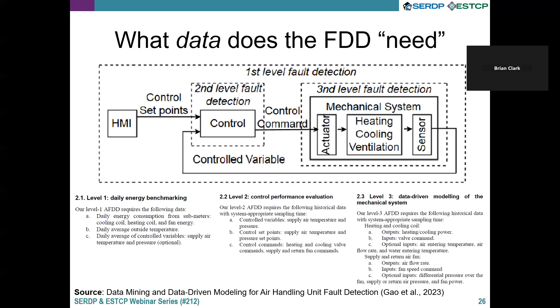So in this study that I'm citing here, shown below, there's even multiple levels of the data collection. There's a first pass in these different feedback loops where we're looking at aggregated daily energy data. And then from there, there's some key performance information from the control system with some different sampling times. And then they go into detail and they look at real data-driven, 15-minute type data that they're pulling here. So even one FDD implementation can pull data at different aggregations from different places, usually operational functional data like what a damper is doing, what this pump speed is, but also sometimes utility data, energy meters, water meters, and so forth.